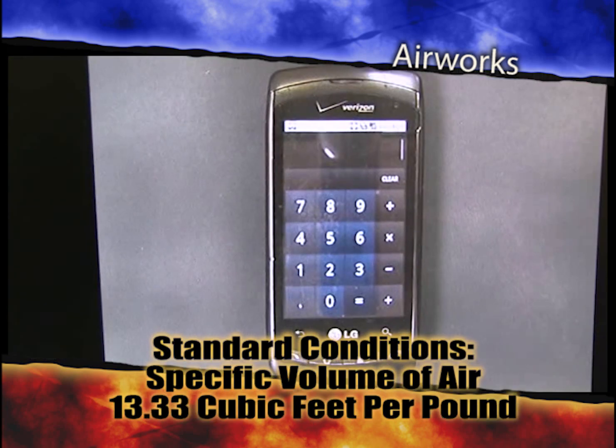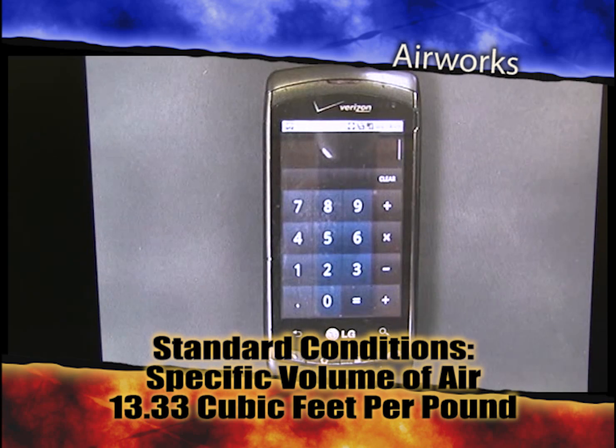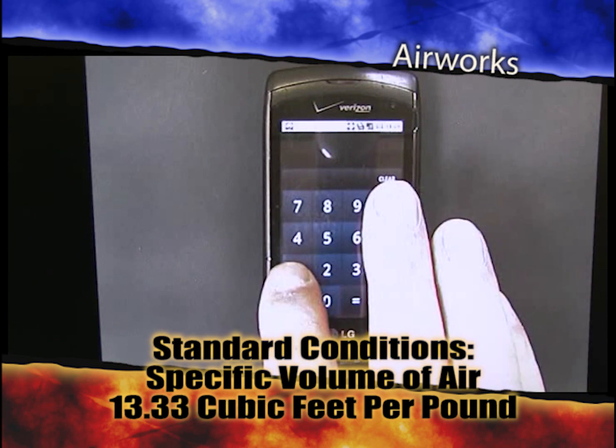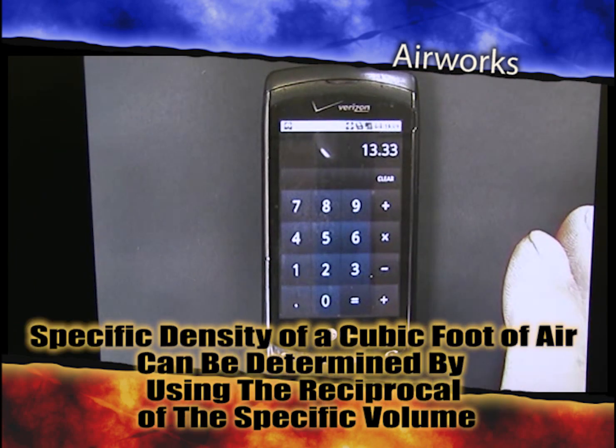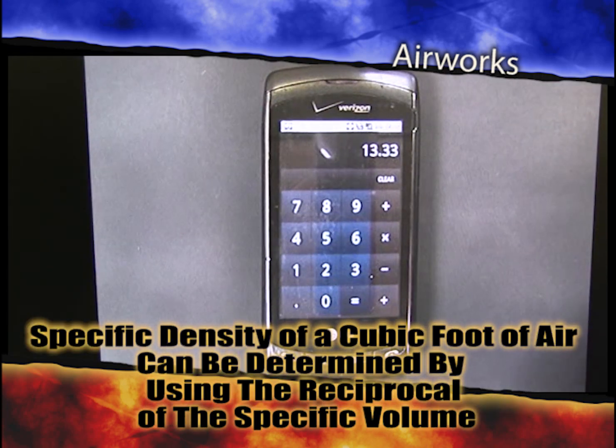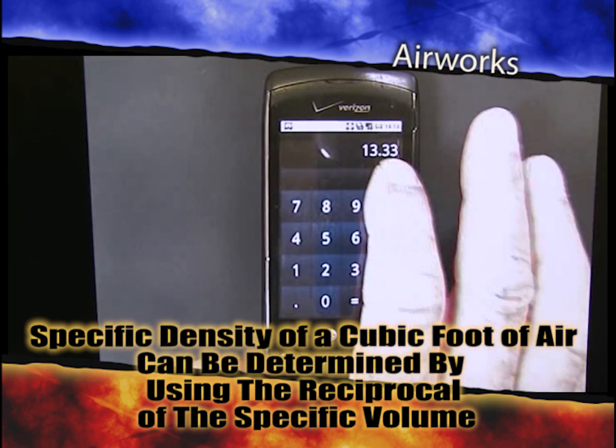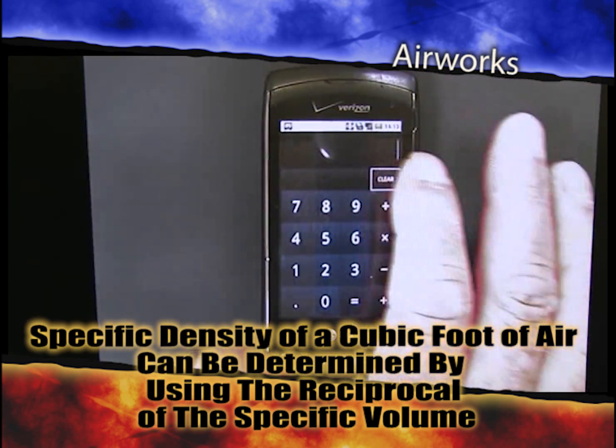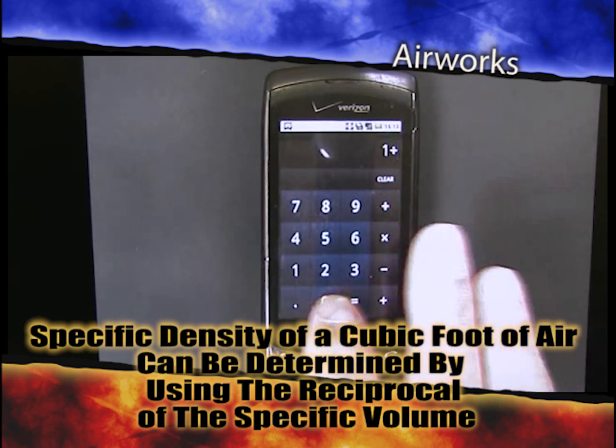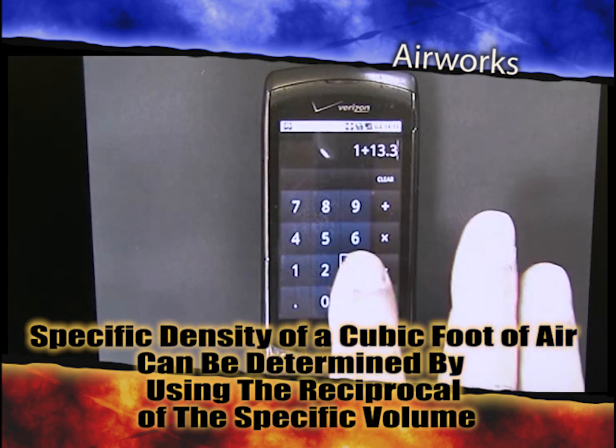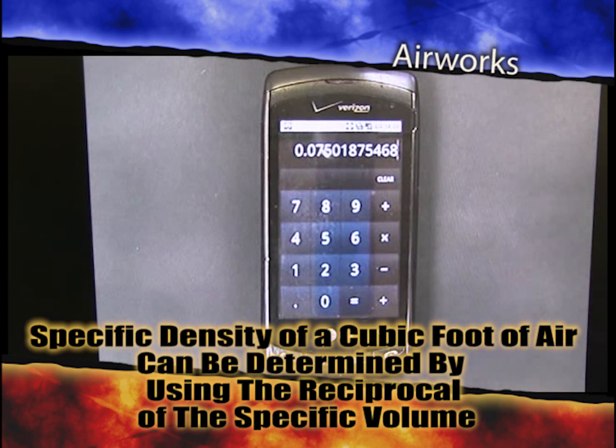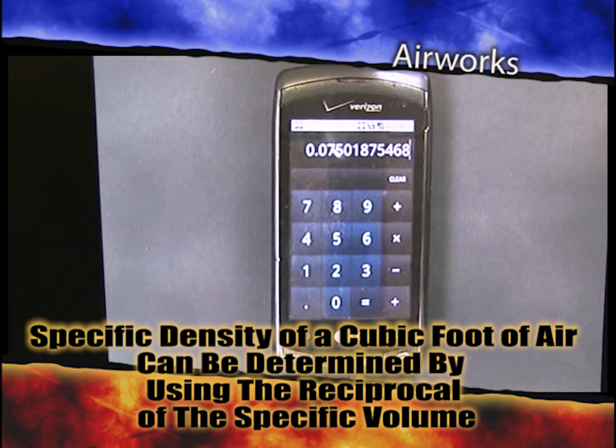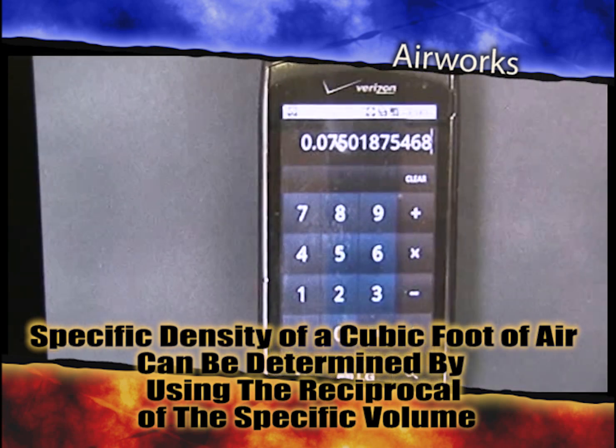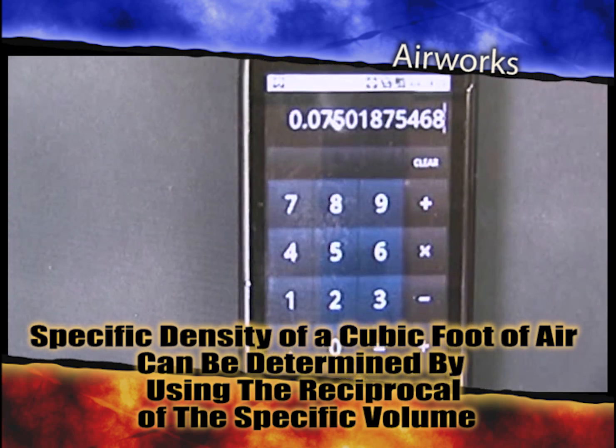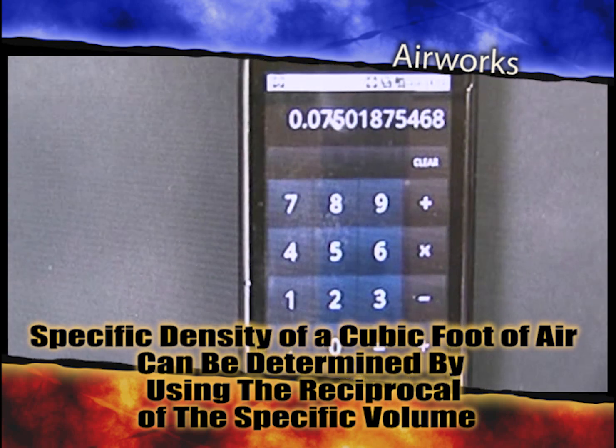All right, as I mentioned, the specific volume of air is 13.33 cubic feet per pound. One of the things that's magic about air is that you can figure out the weight of a cubic foot of air by doing the reciprocal. So what I'm going to do here is I'm going to go 1 divided by 13.33 equals 0.075 and then a whole bunch of other numbers. Notice I'm using my cell phone. I know that everybody out there has one of those and you can calculate with it. It's got a calculator on it.